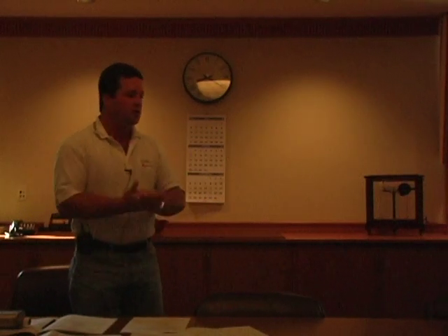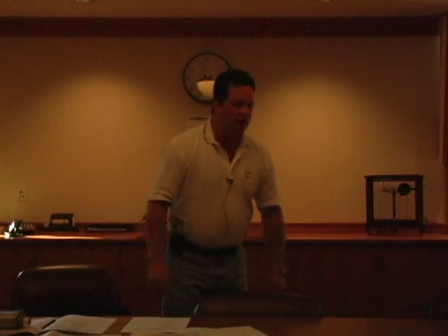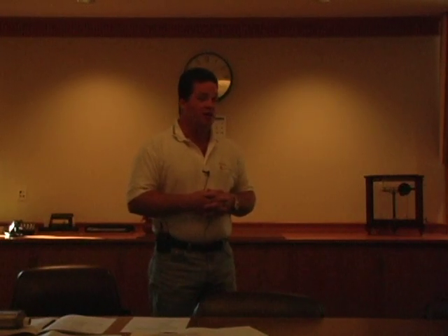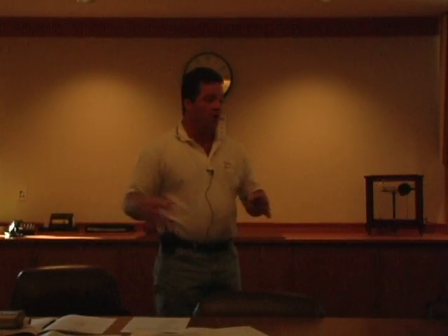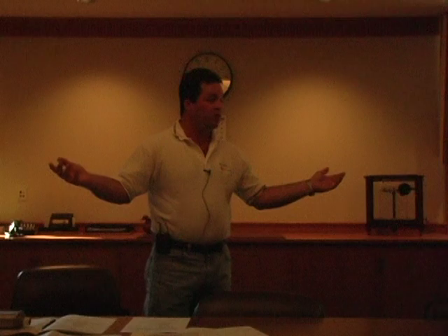As far as storage, very simple. We're up in New England. It's very cold up here during the season. If you have to take one of your tanks out of service and you're not going to be using it right away, or it's going to be down, very easy. We want you to drain the tank down to the floor. We want you to hose out any of the solids or rags around the diffusers and just let them sit. The diffuser here is at the lowest elevation of the manifold, so all the water is just going to come out the bottom.